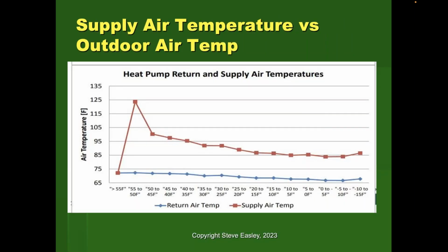Another thing that's important to recognize is what happens to the discharge temperature at the registers. If I look at this chart, this is the heat pump return and supply air temperatures. Just look at the supply temperatures here: where we're at 55 degrees outside, we might have a discharge temperature at that register of 125 degrees. But notice that as the temperature starts to drop outdoors, the temperature at the discharge drops too.